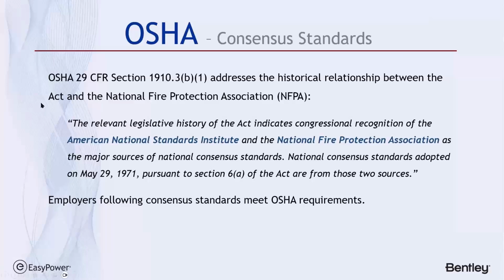OSHA, in their 29 CFR section 1910, describes the connection between the OSHA requirements and the consensus standards. The relevant legislative history of the Act indicates congressional recognition of the American National Standards Institute and the National Fire Protection Association as a major source of national consensus standards. Again, the suggestion is that employers following these standards meet the OSHA requirements. That's why even areas of the market that are not required or covered by OSHA or NFPA 70E may select the path of using NFPA 70E as their guide for electrical safety, because they don't have to rewrite their own individual plan.